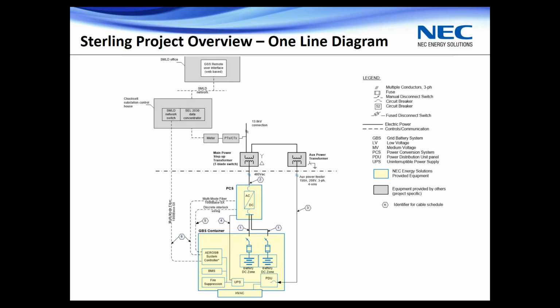The equipment also requires some controls inputs, such as voltage measurements and current measurements from the interconnection point to the utility, and that information is fed back through a data connection. You can kind of see that on the left of the page. There's a multi-mode fiber that we're running between the Sterling substation control house and the AEROS system in the GSS container. So those three things are essentially the connection to Sterling's existing system. It's the actual power connection to the grid, the auxiliary power connection to power up the unit, and the data connection in order to be able to exchange information back and forth between Sterling and the NEC system.